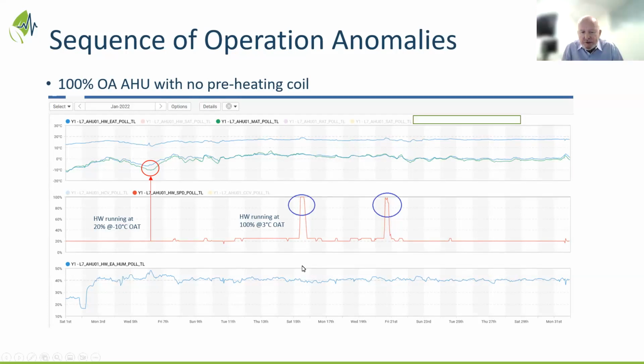Sorry, Amity, what's the problem caused when it goes to a higher speed? It uses more power on the wheel, but that's not a big deal. Other operational issues that arise? There are operational issues because now you can't control the supply temperatures to deliver consistently. So it just fluctuates, and then the heating coil comes on or other factors come in, which again makes life difficult for the operations team. Thank you.